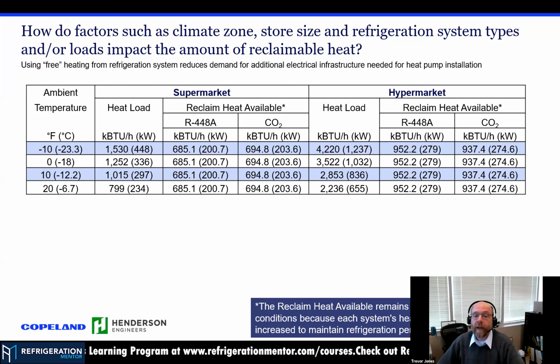Now, one thing is the available heat off of the system remains fairly flat in the coldest periods because you're running down towards your minimums. That's right. Because that high pressure valve is maintaining a certain temperature and pressure in that gas cooler. So that's all you have of whatever heat that is, whatever that high pressure valve is doing.